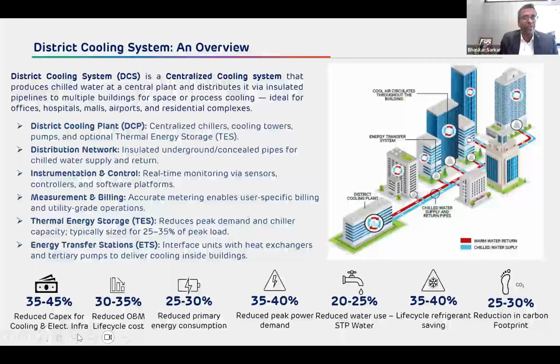So if we see what the benefits are in a nutshell, there is a reduced capex for cooling and infra, because the capital expenditure, the total TR units of equipment required in a centralized plant, due to load diversity of the various consumption points, is very low. In a commercial we need about 70% of the total load requirement, which would have been consumed by conventional. And in a residential, it is as low as 20 to 25% of the total demand, for which we have to actually make provision for the plant capacity. So that actually reduces the capital expenditure for not only the cooling infrastructure, but also the associated electrical infrastructure by about 35 to 40 to 45%. So this is the first saving, or first positive impact of the district cooling system, that the capex gets lowered.